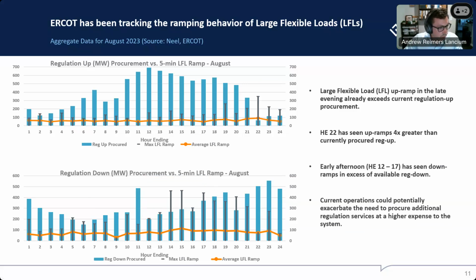And what this chart is showing is that there are already a lot of intervals where ramp up is exceeding up ramp regulation and ramp down is exceeding down regulation. If you look on the top chart near the right of the chart, you have a lot of situations where the large flexible loads are ramping faster than up regulation is able to respond to. And similarly, in the middle of the day, we're having a lot of situations where down ramp is happening faster than the down regulation is able to respond to. This problem is only likely to get worse as more loads like this energize, leading to reliability issues if they continue to exhaust regulation beyond what ERCOT procures.